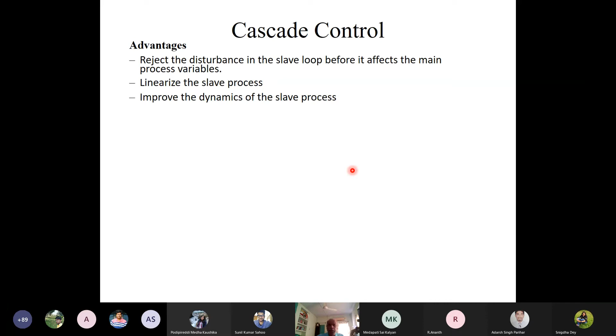For implementation, the slave process must be at least 3 times as fast as the master loop in terms of response time. This is very, very important when we implement cascade control strategies. We can implement the cascade control strategies only where the slave process is at least 3 times faster than the master process.